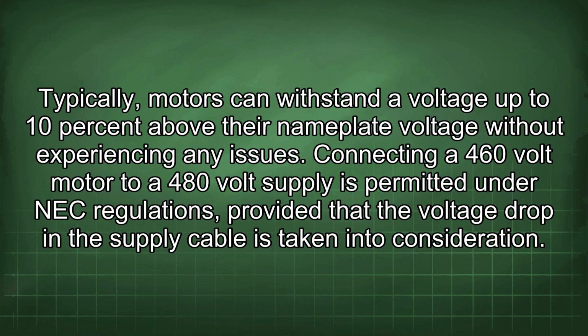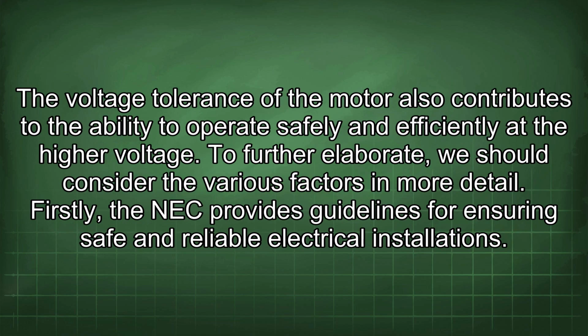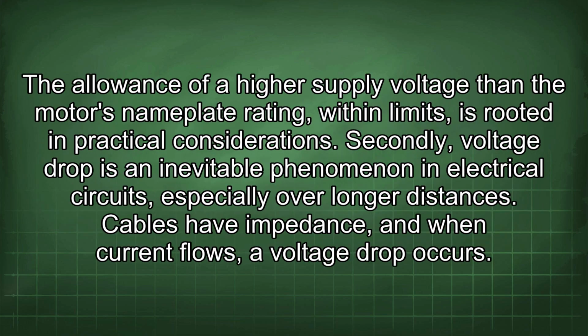Connecting a 460-volt motor to a 480-volt supply is permitted under NEC regulations provided that the voltage drop in the supply cable is taken into consideration. The voltage tolerance of the motor also contributes to the ability to operate safely and efficiently at the higher voltage. To further elaborate, we should consider the various factors in more detail. Firstly, the NEC provides guidelines for ensuring safe and reliable electrical installations. The allowance of a higher supply voltage than the motor's nameplate rating within limits is rooted in practical considerations.